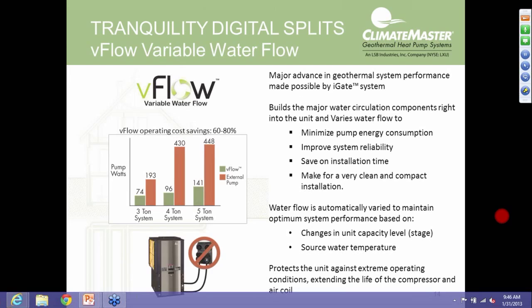With the VFlow, again, with that variable speed pump, one of the biggest advantages of that variable speed pump is pump watt savings. And you can see here in this graph, especially as we get to our larger systems, where we're typically into more pumps. We're typically maybe putting a 2-pump flow controller on a 4 or 5-ton system, and in some cases it may be 2 Grundfos 116 pumps.